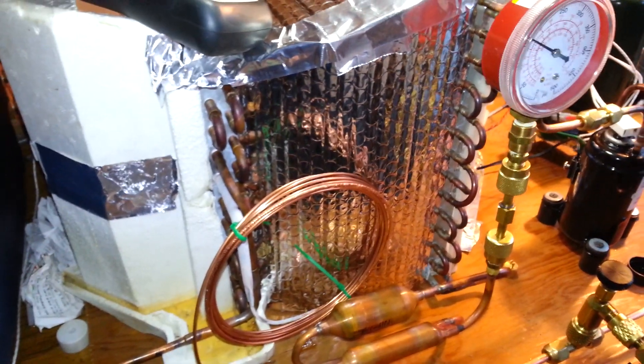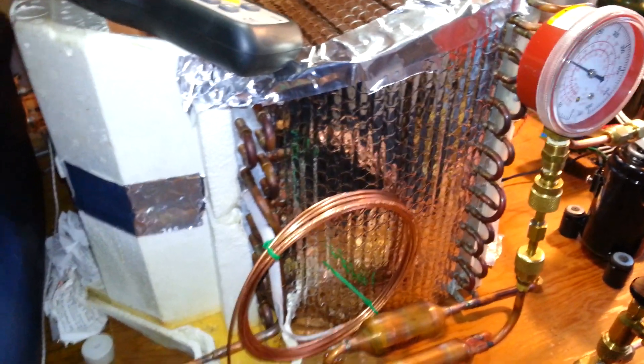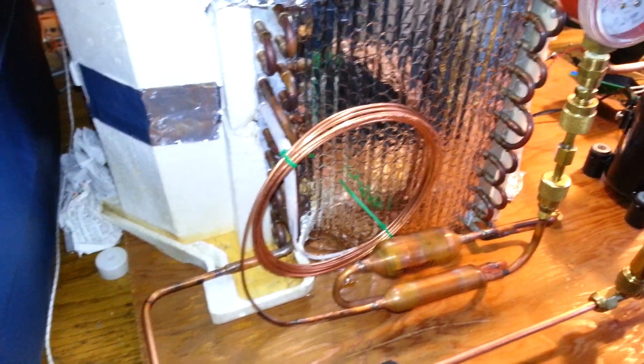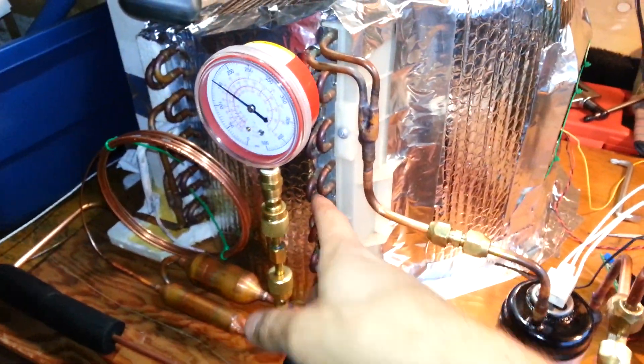So there's liquid backed up in here. The refrigerant charge is, in this case, in excess, but it doesn't really matter. There's too much cap tube, too much restriction there. Pressure's too low on the low side, too much liquid backing up on the high side.